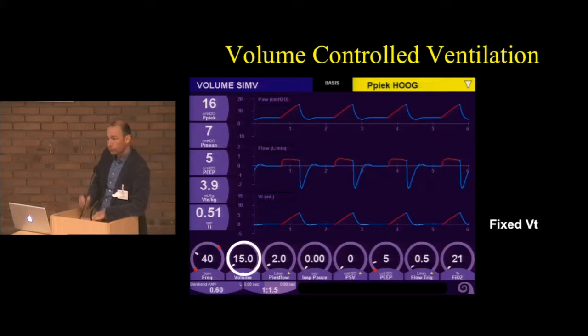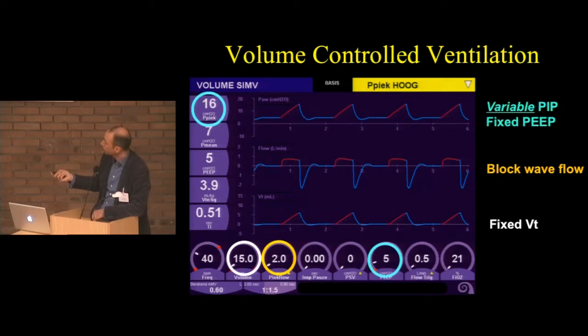So how does true volume-controlled ventilation work? It's a different modality from time cycle pressure limit. It's been the primary mode that's been used in the adult population and to a larger extent also in the pediatric population. So the big difference with time cycle pressure limited is now the clinician will set a fixed tidal volume, in this case 15 mLs. You still have to set your PEEP. It will deliver this tidal volume not through a decelerating flow, but through a block wave flow, which is different from pressure-controlled or pressure-limited ventilation.